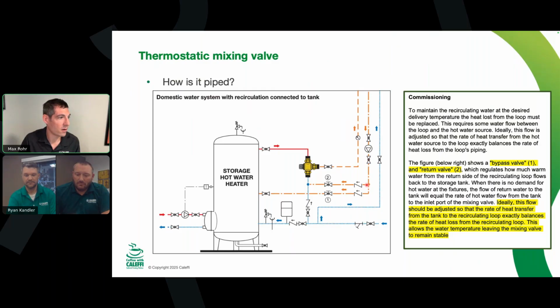We lost 3 degrees of temperature. What we want to figure out is how much of that water goes right back out to the system, and how much goes back to the tank. The adjustment of these two valves prevents either recirc creep, where the recirc line is increasing in temperature all the time, or recirc droop, where in periods of low occupancy the recirc line bogs down. In that scenario, we didn't have enough coming back to the cold inlet to go out. In a recirc creep scenario, too much goes back to the cold inlet, and we're mixing hot with hot, and we can exceed our set point. So then we need to adjust this.